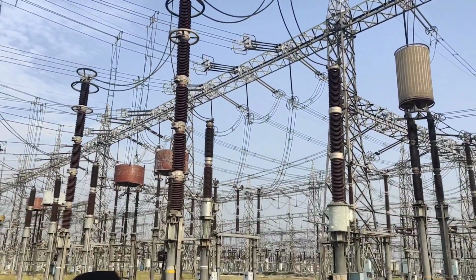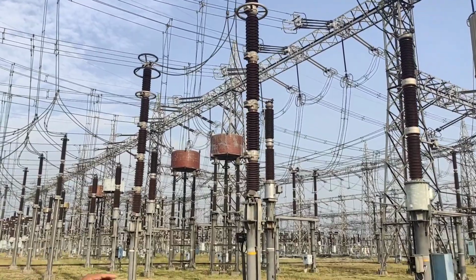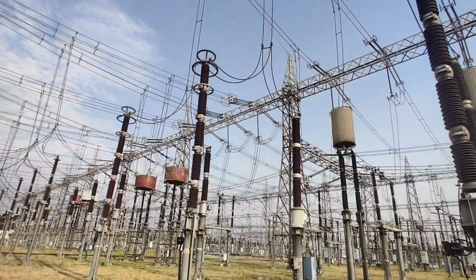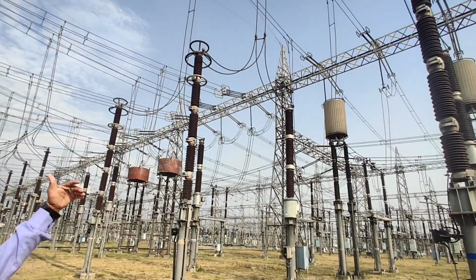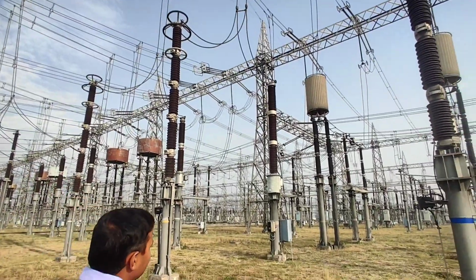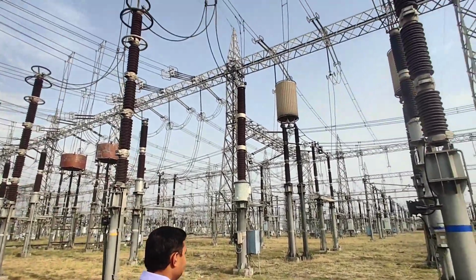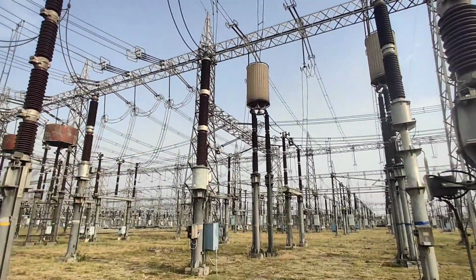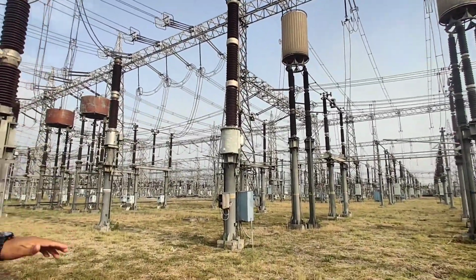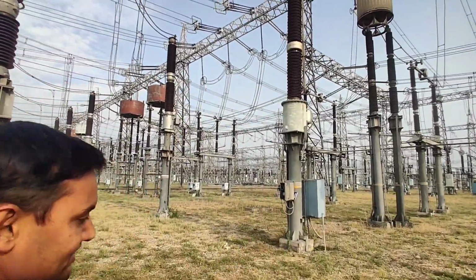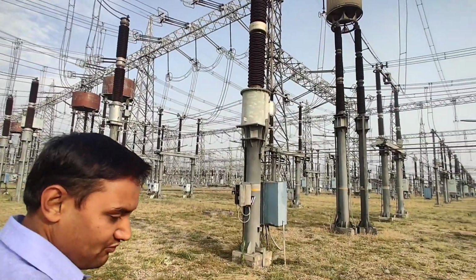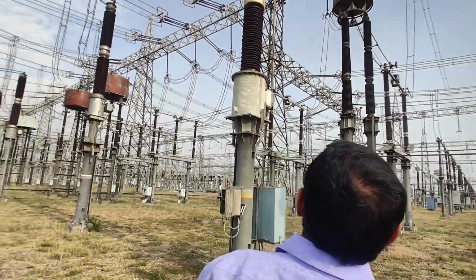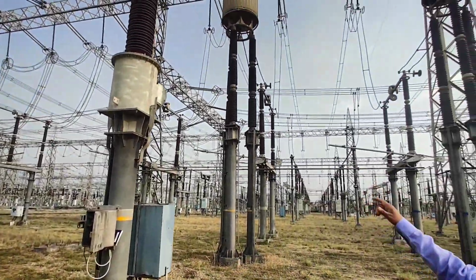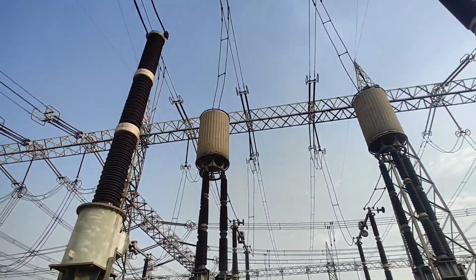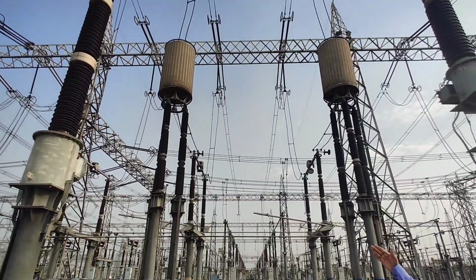The first equipment where the transmission line enters into the substation is the lightning arrestor or surge arrestor. After this lightning arrestor, the next equipment which comes is the CVT or capacitive voltage transformer. We will see why the capacitive voltage transformer is used at a somewhat later stage. And after this capacitive voltage transformer, the transmission line is now connected to the wave trap.